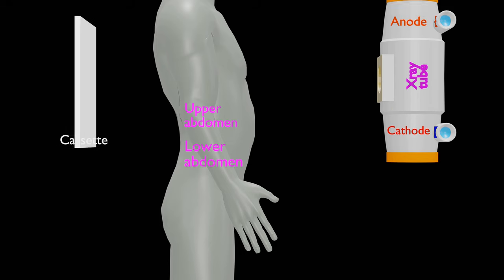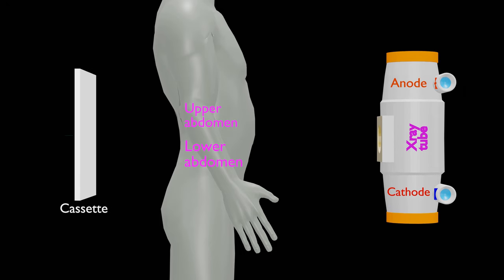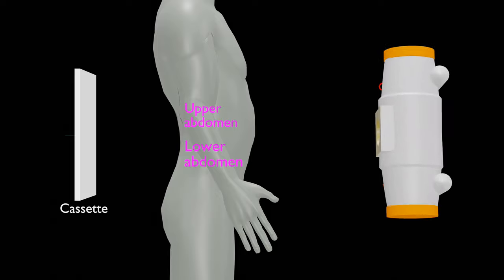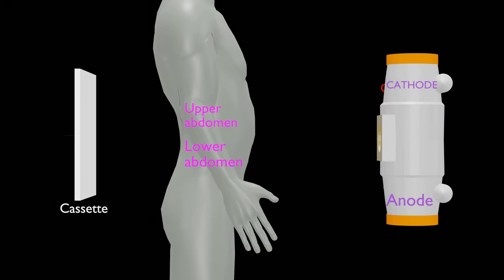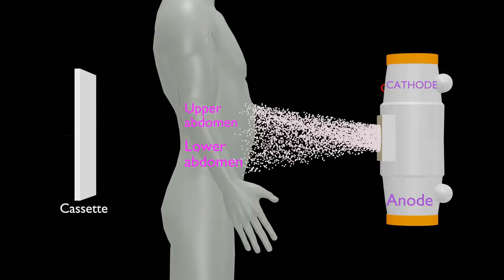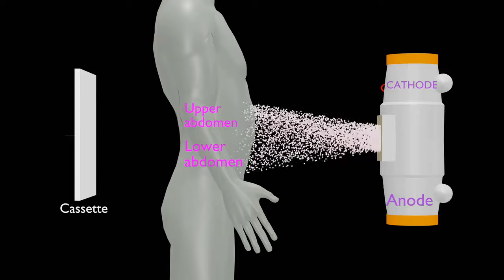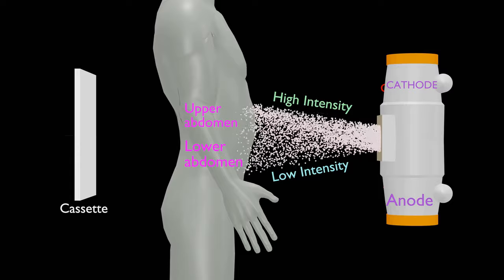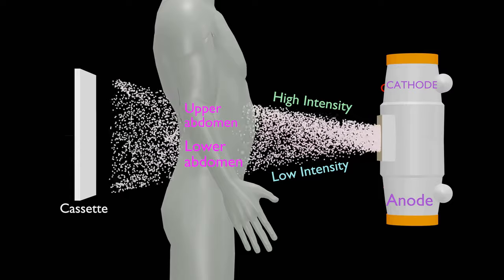In the abdomen, anatomy is thicker towards upper abdomen and thinner at lower abdomen or pelvic area. So, we need to keep cathode of x-ray tube superiorly. By doing so, thicker upper abdomen will receive higher intensity of x-rays, and due to higher thickness, upper abdomen will attenuate more comparison to lower abdomen.